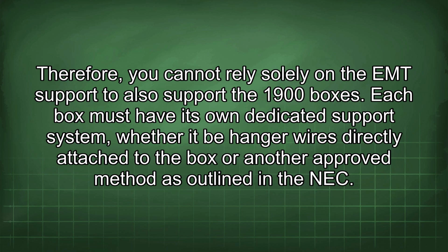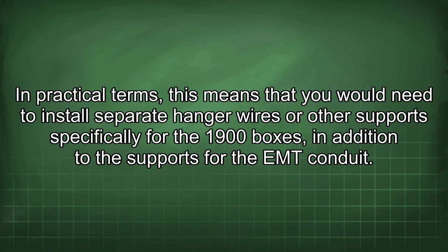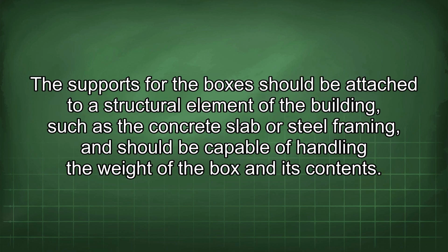Each box must have its own dedicated support system, whether it be hanger wires directly attached to the box or another approved method as outlined in the NEC. In practical terms, this means that you would need to install separate hanger wires or other support specifically for the 1900 boxes, in addition to the supports for the EMT conduit. The supports for the boxes should be attached to a structural element of the building, such as the concrete slab or steel framing, and should be capable of handling the weight of the box and its contents.